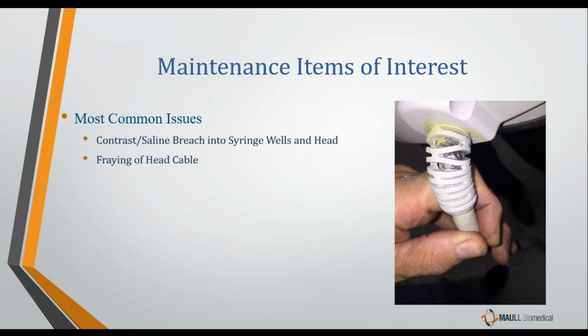Now, if you'll recall, whenever we are filling the syringe, the injector head is pointed up. Whenever we are injecting, the injector head is pointed down. So every single time they fill and inject, they are tilting that injector head up and down. So that head cable coming out of the injector head takes a lot of flexing at the point of entry where the cable goes into the head. And this is not an unusual sight at all right here. The head cable just sort of wearing off with all the flexing that's taken place on it over the years.